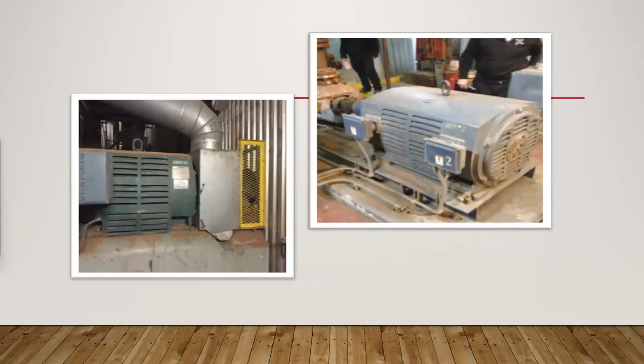But today, with all of the peaking needs in the industry, you need to look at the amount of power that you're able to produce on out, because that gives you more and more production capability in a generation plant. This happened to be the big draft fans. We also look at the nameplates properly and the information, so that a VFD is properly applied to it to make sure it meets the proper voltage, winding capabilities, cooling properly in the motors, depending on the type of load it is. These were the 750 horsepower boiler feed pumps that were brought into the system.